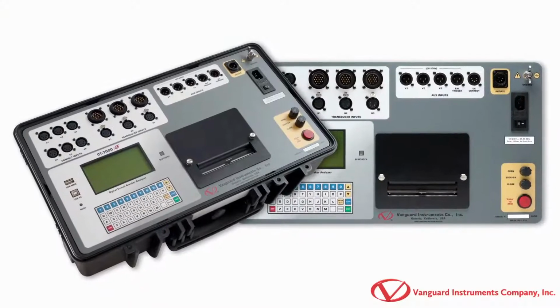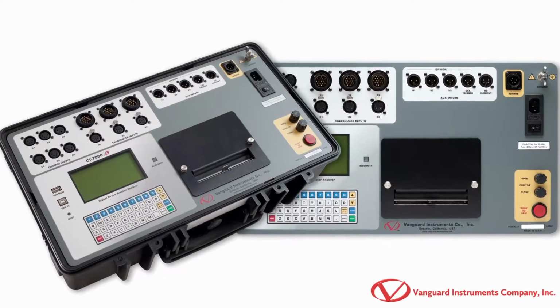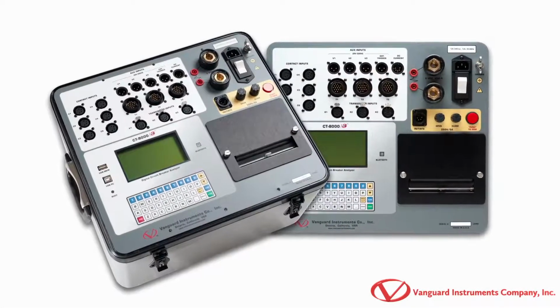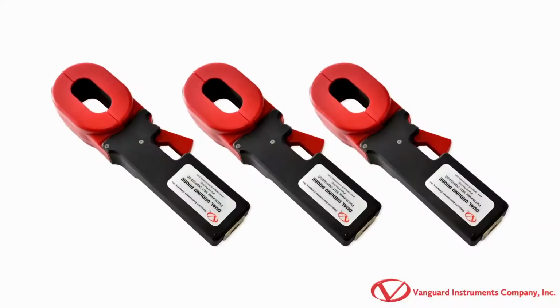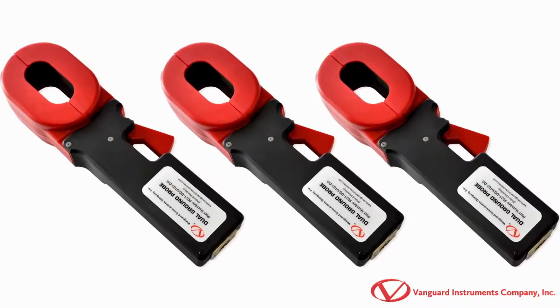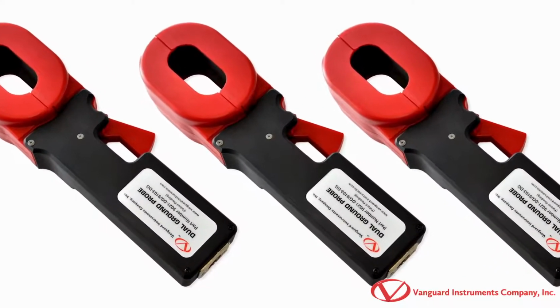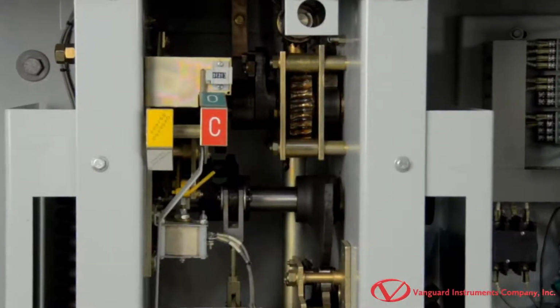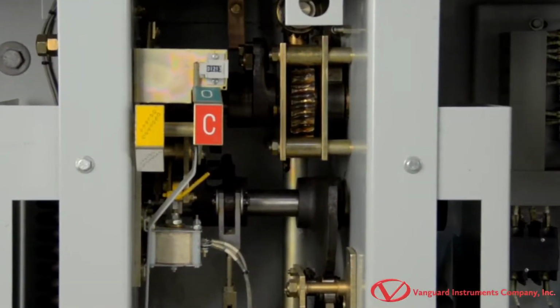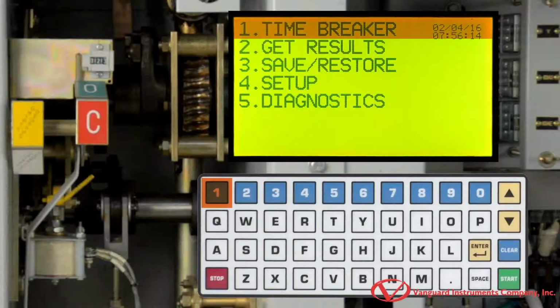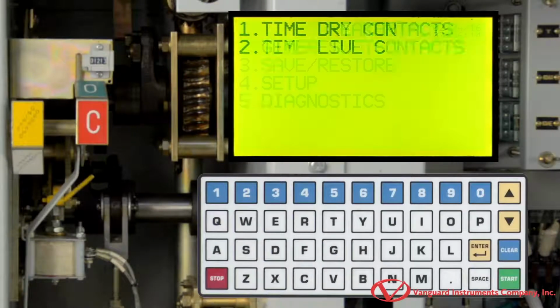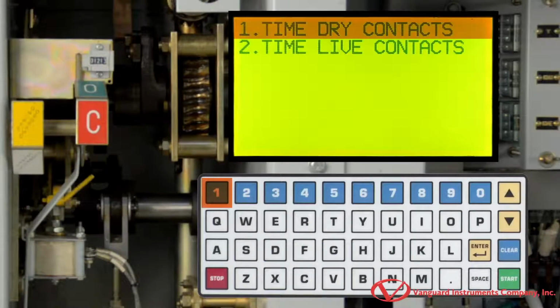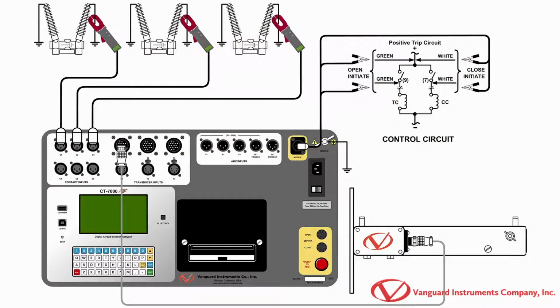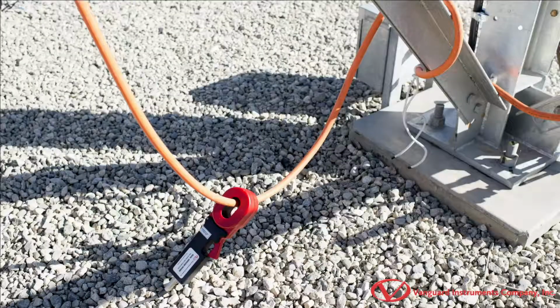Vanguard Instruments' state-of-the-art CT7000S3 and CT8000S3 circuit breaker analyzers offer a dual ground option for testing circuit breakers with both sides of the breaker grounded. With this option, users can safely perform tests with both sides grounded using the same procedures they are already familiar with for performing traditional tests. Vanguard's dual ground testing of circuit breakers requires the user to connect a measurement probe on one side of the grounding cable in each phase as shown here.